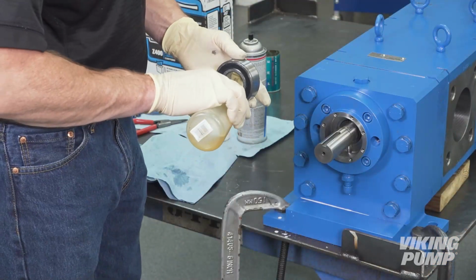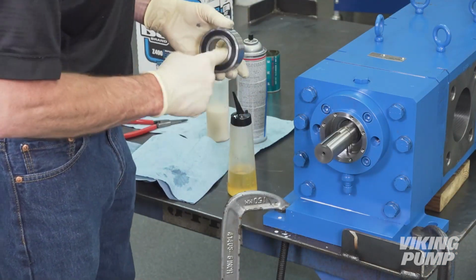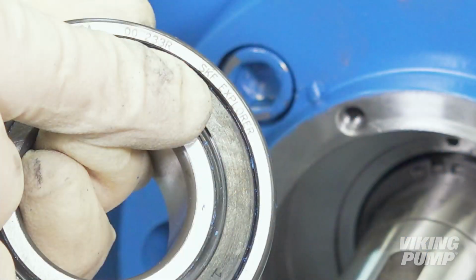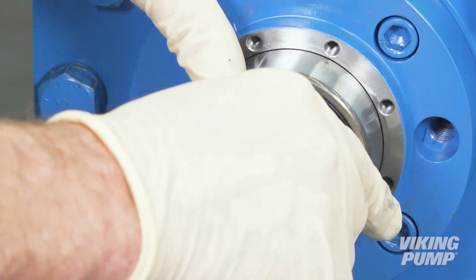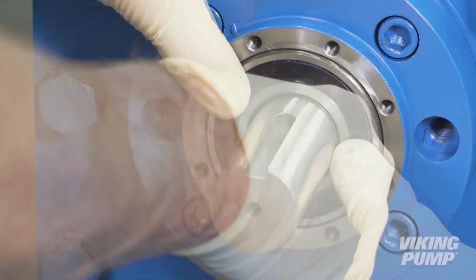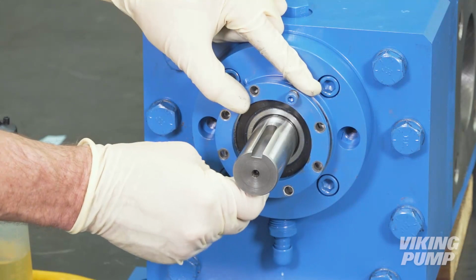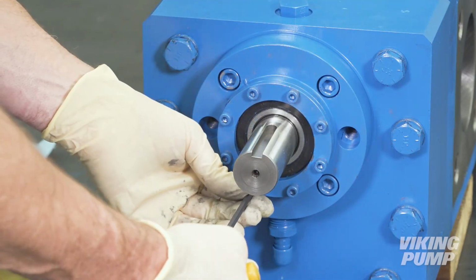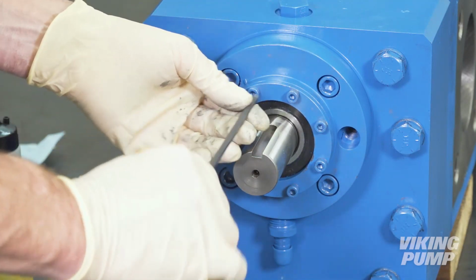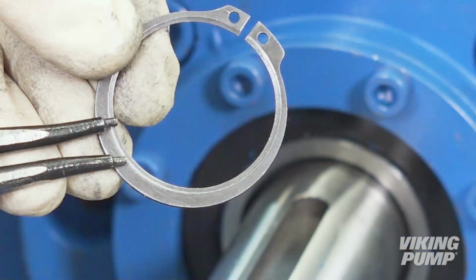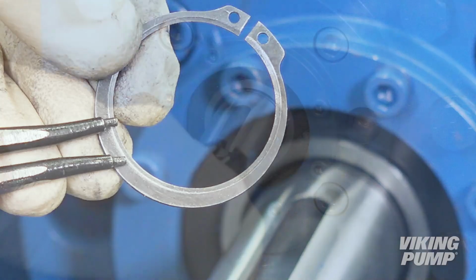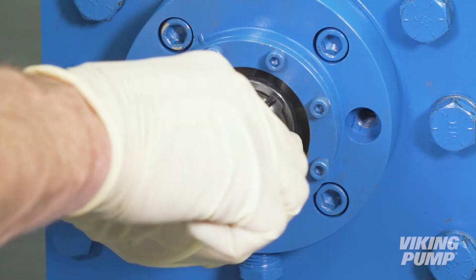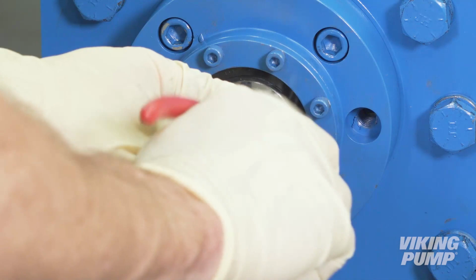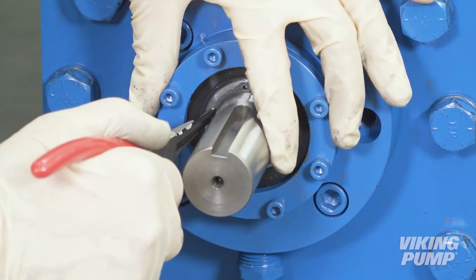Next, coat the thrust bearing in light oil and install onto the shaft. Make sure the printed letters on the outer race of the bearing are facing outward. Install the bearing end cap. Tighten the cap screws in a star pattern. Install the beveled retaining ring with the bevel facing outward toward the motor end of the shaft. Pulling the shaft away from the pump while installing the beveled snap ring will ensure proper installation into the groove.